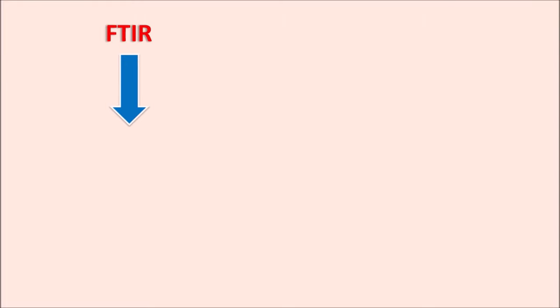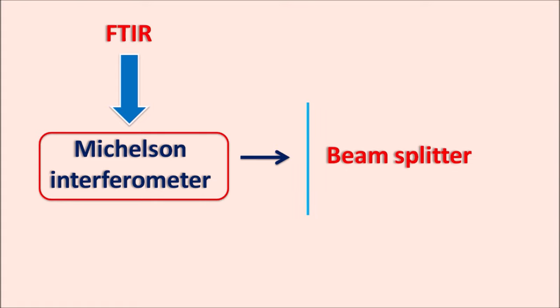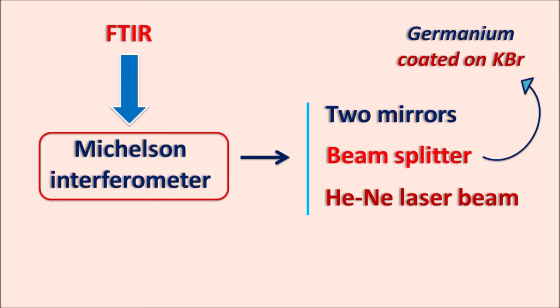An important component within the FTIR is the Michelson interferometer. This component acts like a monochromator but works by a different mechanism. It has three important components: a beam splitter that splits incident radiation into two equivalent beams, a helium-neon laser beam responsible for accuracy in FTIR, and two mirrors — one movable and one fixed. The beam splitter is made of germanium coated on potassium bromide.